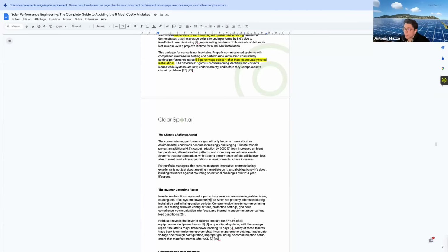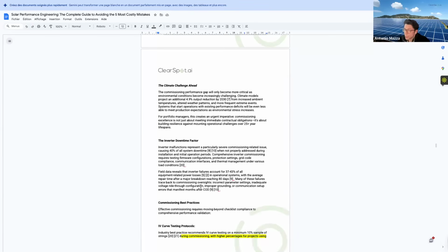So that reveals indeed that inverter failure accounts for 37-43% of all equipment-related power losses in operational systems, with an average repair time in major breakdowns reaching 80 days. Many of these failures trace back to commissioning oversight: incorrect parameter settings, inadequate voltage ride-through configuration, improper grounding, communication setup errors that manifest months after COD.